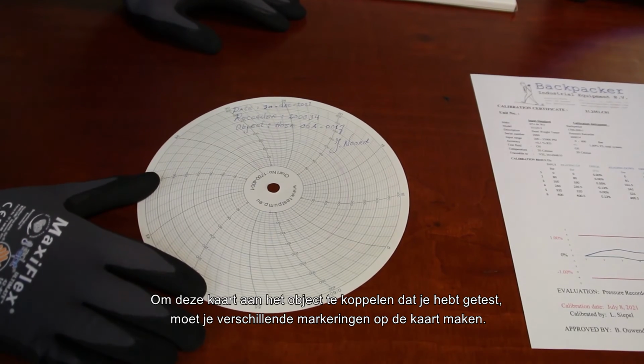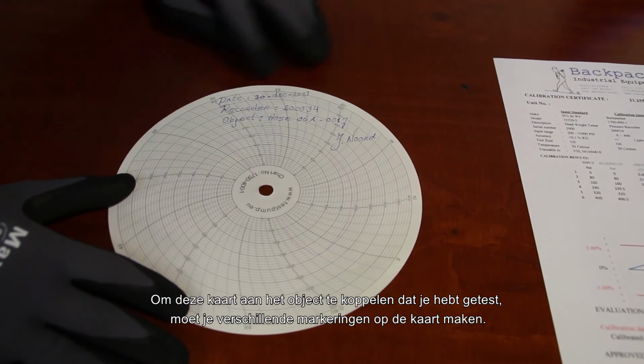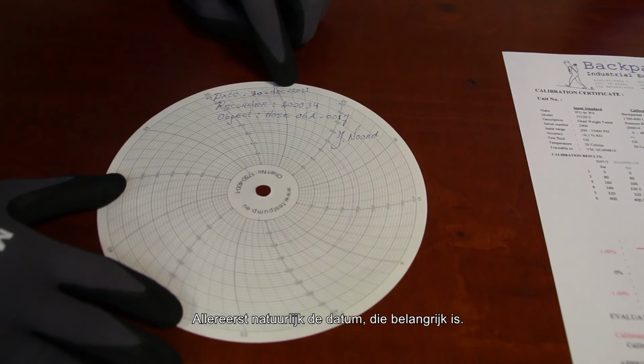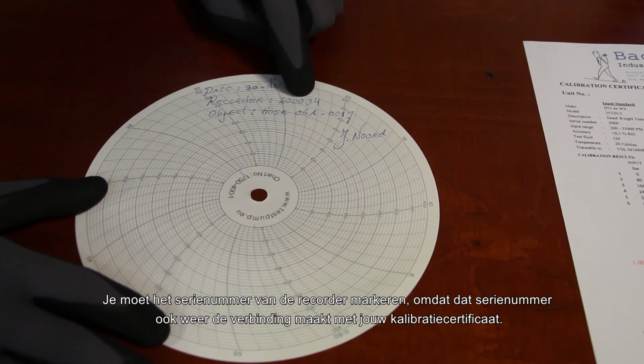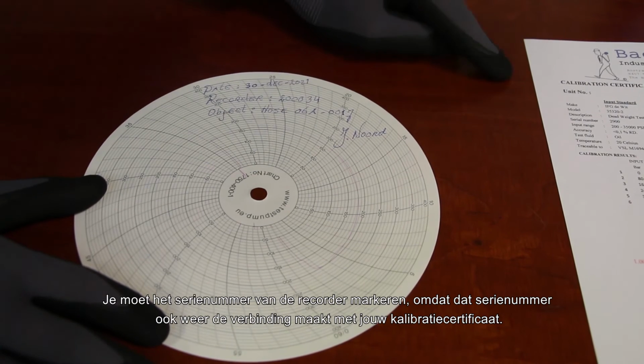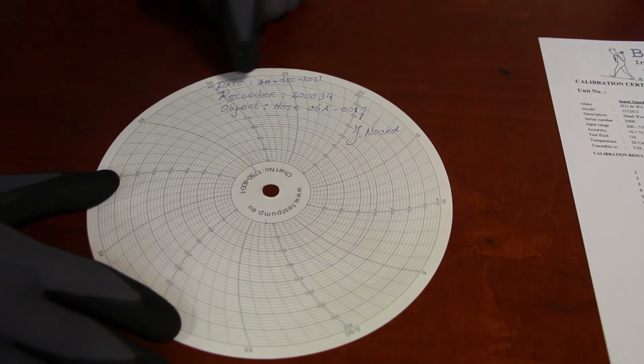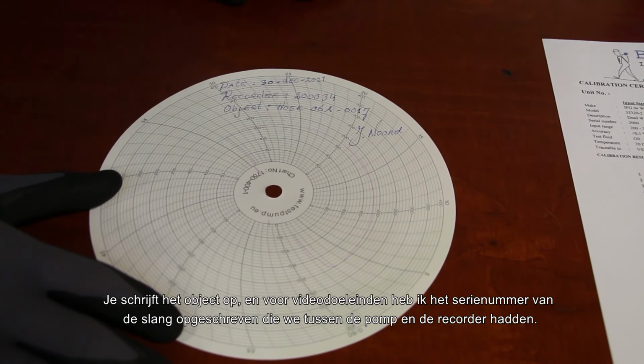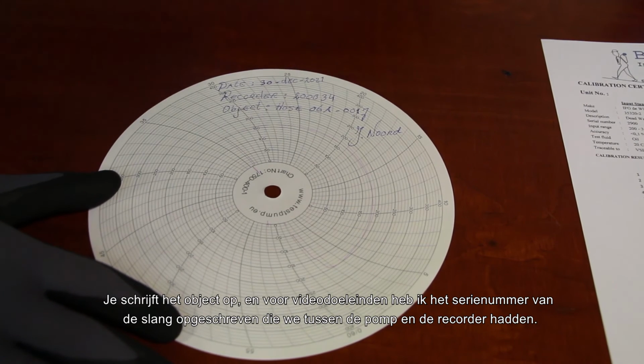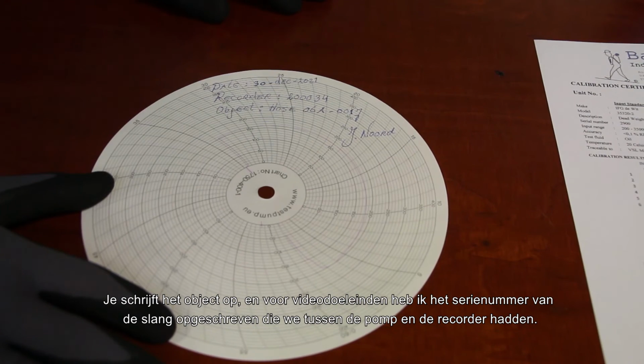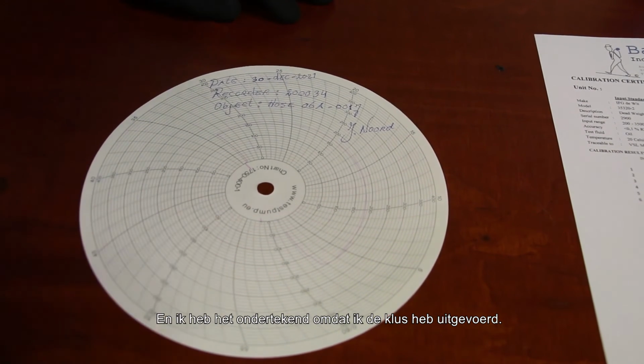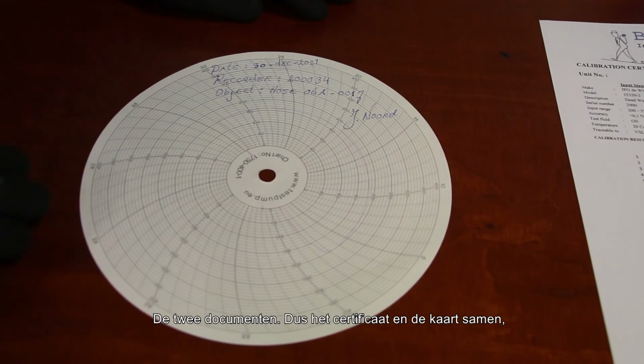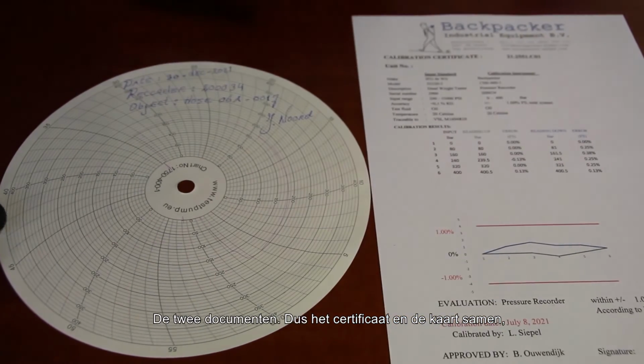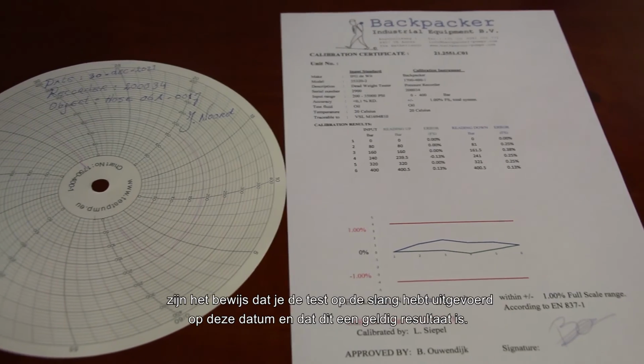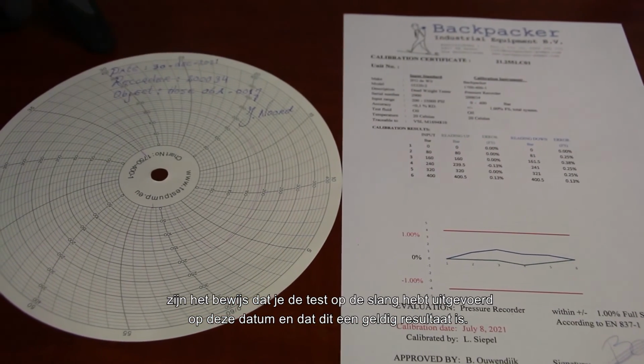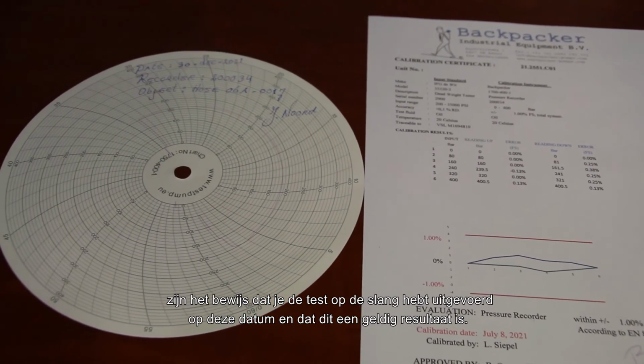To link this chart to the object you've been testing, you need to make several markings on the chart. First, of course, the date. That's important. You need to mark the serial number of the recorder, because that serial number again relates to your calibration certificate. You write down the object, and for video purposes I've written down the serial number of the hose that we have had between the pump and the recorder, and I've signed it so that I carried out the job. The two documents, the certificate and the recorder chart together, are your proof that you carried out the test on the hose at this date and that this is a valid result.